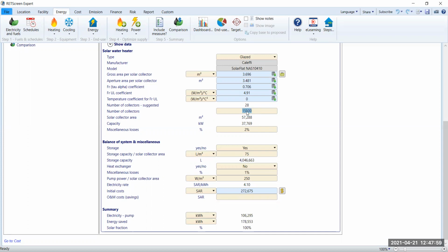Oh, sorry, that should have been, I wanted it to be 50 only. So, going to something like 70% is more than enough. Normally, you would accept a value of the solar fraction on the order of maybe 0.5 to 0.7, like 50 to 70% is going to be good enough. And the kind of benefits that we can get from here are a lot.